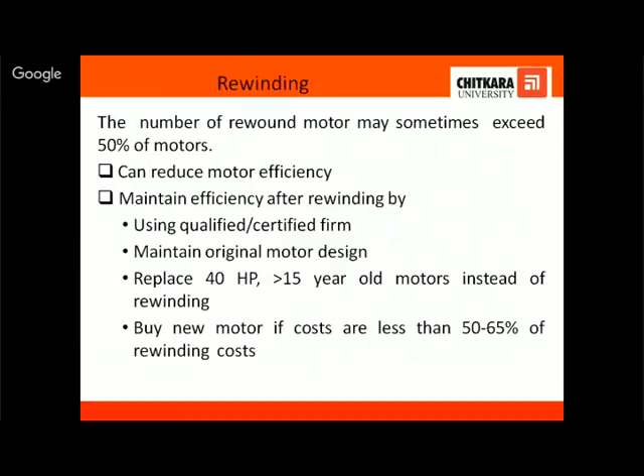Sometimes we should compare the test results with the test results of the original motor. So once the motor is rewound, ask the person to perform the test in my presence, take the data sheets and the test reports, and compare with the original. The original design should not be changed after the rewinding, otherwise you will not even come to know what harm it is doing to the industry in terms of energy consumption.